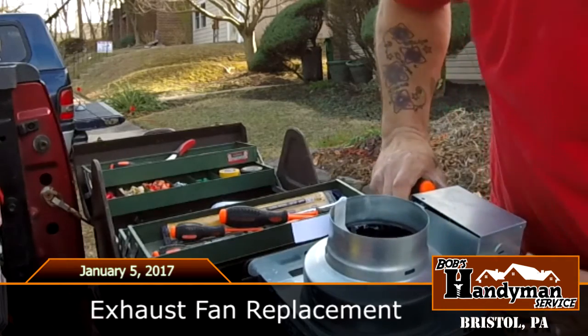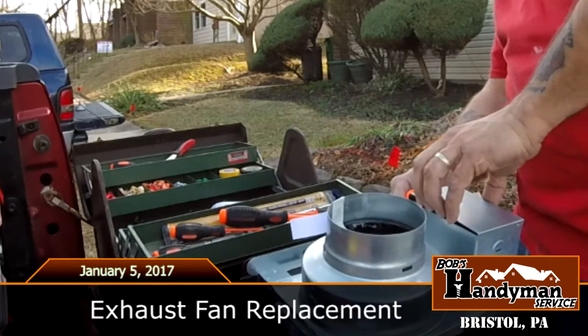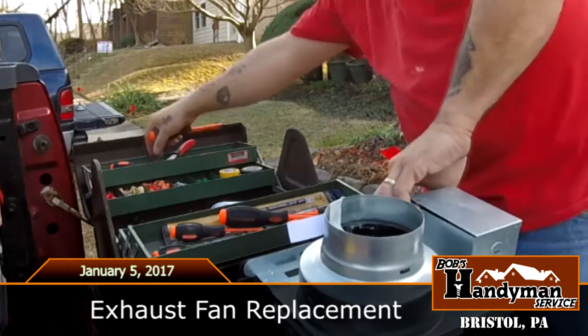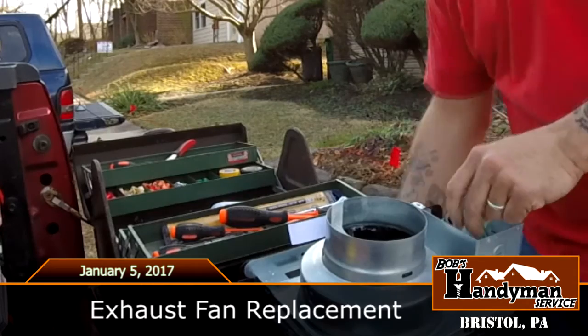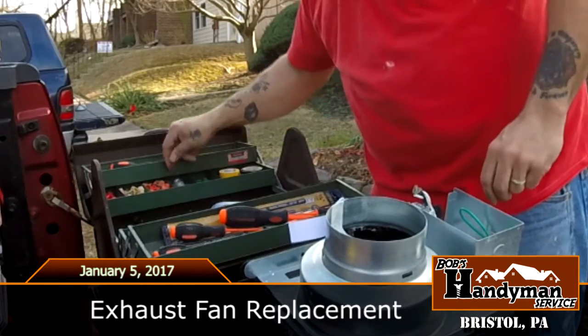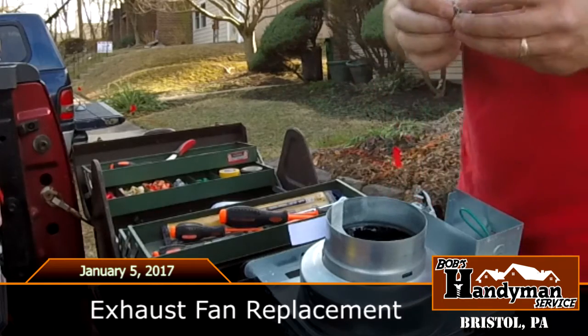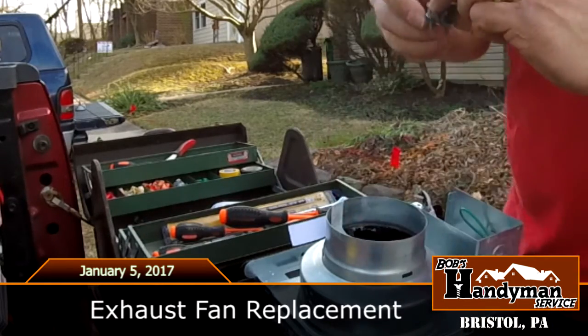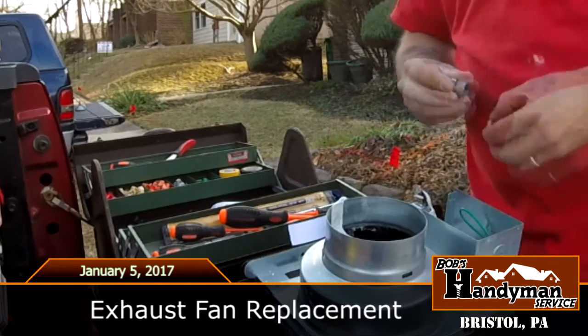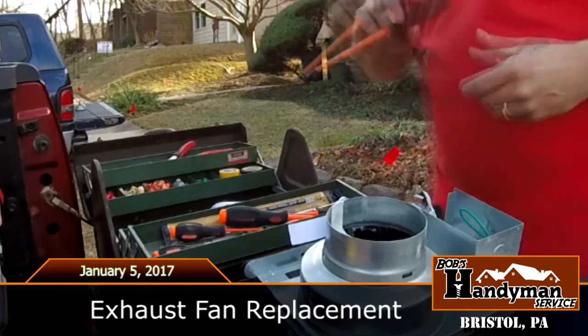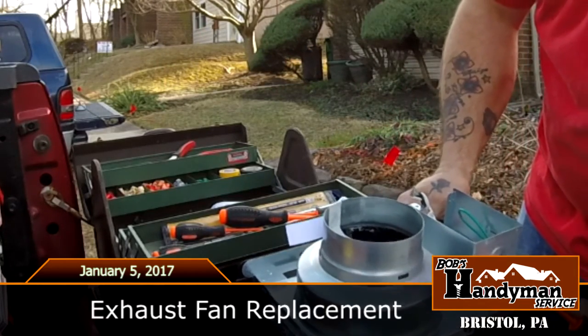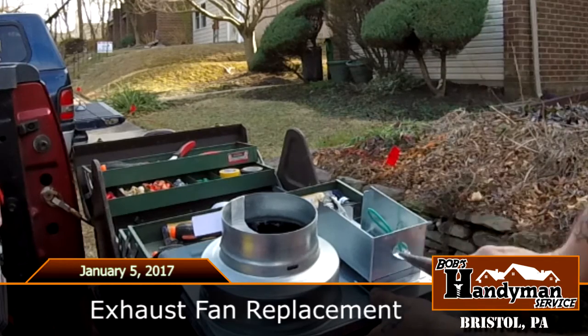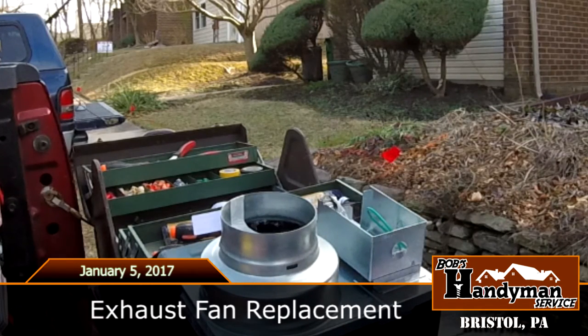Sit the chassis on something secure. Using a screwdriver, remove the one single set screw and open the attached electrical box. Prepare to install a Romex connector, which holds the wire in place. This is what they look like. Before doing so, you'll have to remove the knockout plug. This is easily done with a flathead screwdriver and a pair of needle nose pliers. Do not reinstall the cover on the electric box until after we make the electrical connections inside the home.